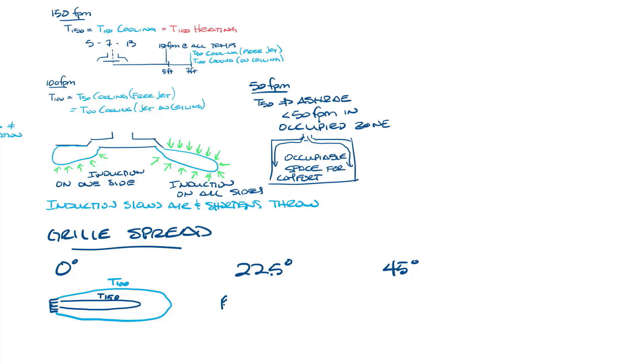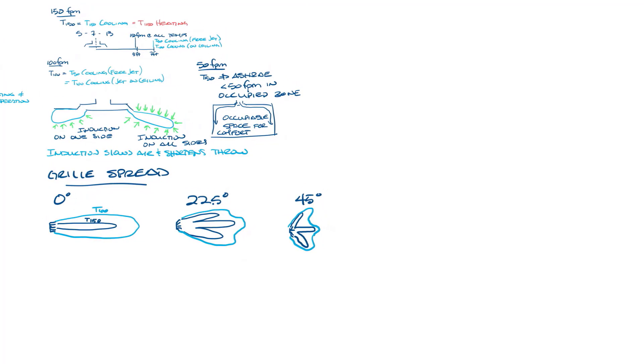As you start spreading the throw, you get kind of three separate little jets of T150 and T100 surrounds that. And then at 45 degrees, it's even shorter and wider. So as the spread goes up, the throw is shortened. This is because at 22.5 and 45 degrees, there's more induction into the jet, so you have shorter throws.